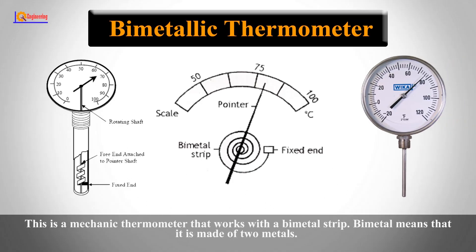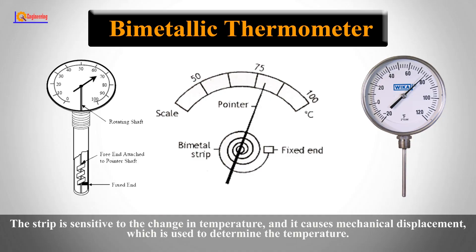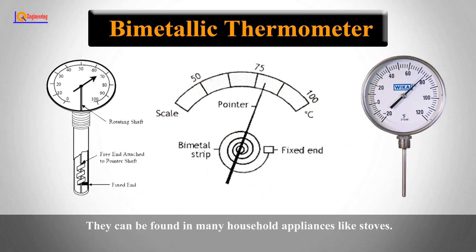Bimetallic thermometer. This is a mechanical thermometer that works with a bimetal strip. Bimetal means that it is made of two metals. The strip is sensitive to changes in temperature and causes mechanical displacement, which is used to determine the temperature. These thermometers are perfect for higher temperatures, as they become less sensitive and accurate at lower temperatures.